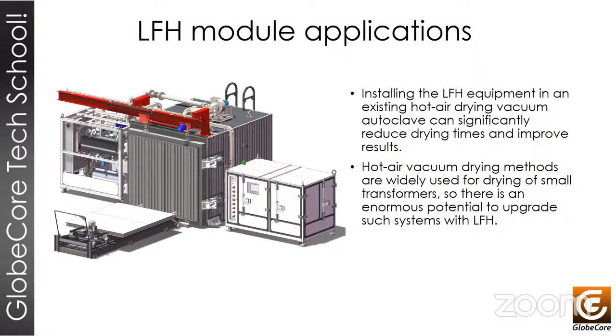If a small dryer with hot air circulation consumes 50 kilowatts and operates for 80 hours, the total energy consumption for drying a small transformer is 4,000 kilowatt-hours. If the drying time is reduced by 50%, the energy saving in the event of drying one transformer by the LFH method will amount to at least 2,000 kilowatt-hours.